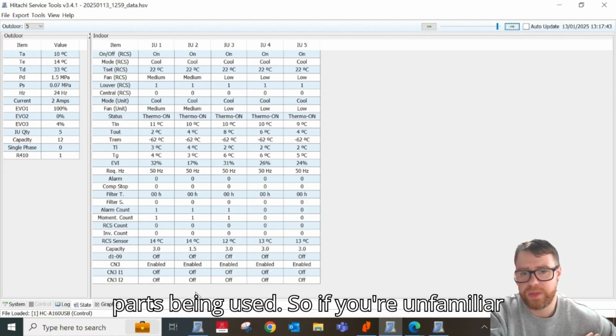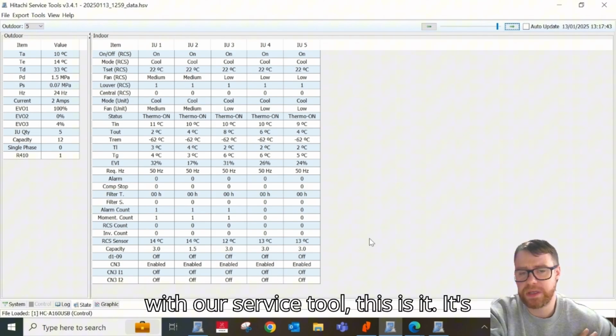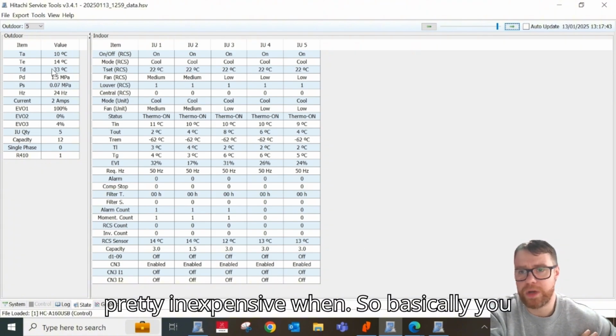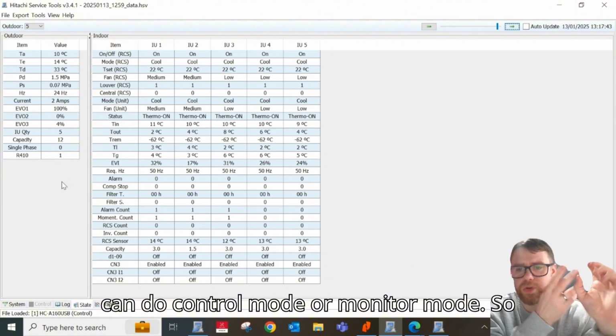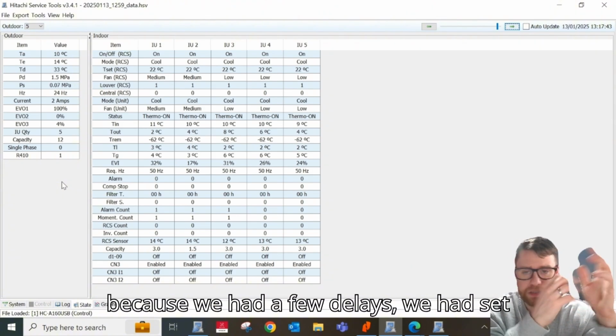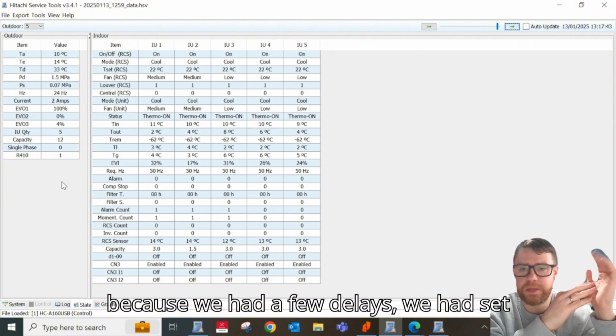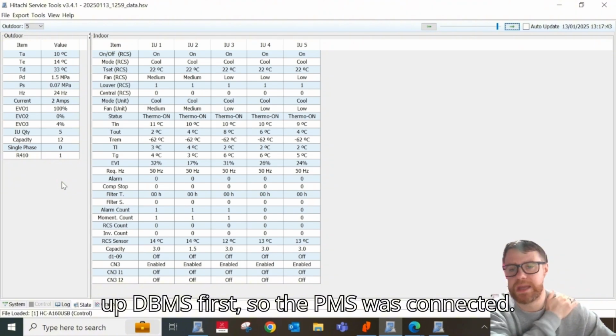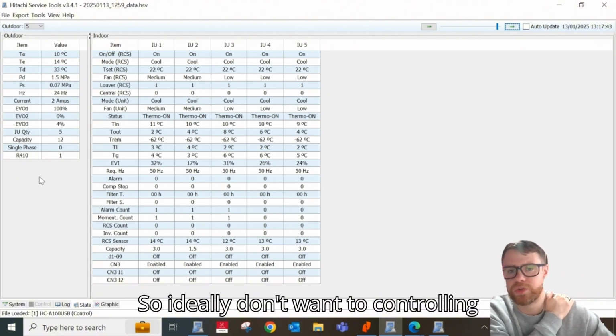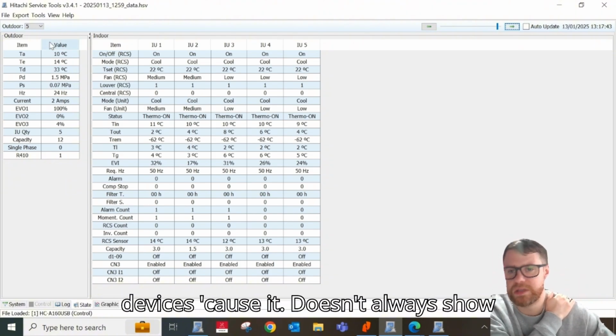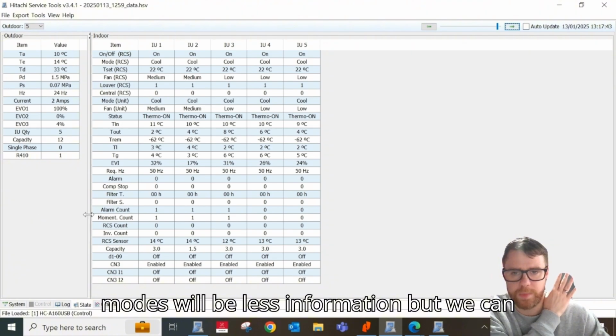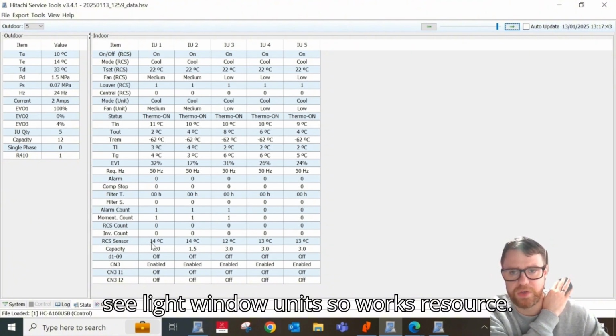If you're unfamiliar with our service tool, this is it. It's pretty inexpensive. You can do control mode or monitor mode. Because we had a few delays, we had to set up the BMS first. So the BMS was connected. Ideally, you don't want to be controlling devices because it doesn't always show the details properly. So we're in monitor mode, so we've got a bit less information, but we can see all our indoor units.